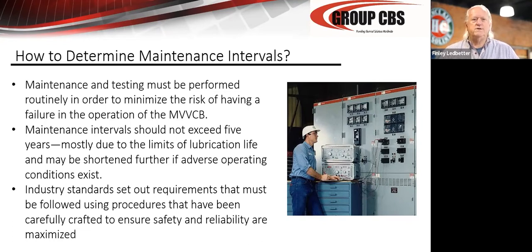I was at a power plant a few years ago, and they had spare breakers sitting on the side that had 20, 30, 40, 50 operations on them that were 20 years old. And they had breakers in service with 3,000 operations on them. What kind of sense does that make? It makes no sense. So you need to get these high operation breakers out and get these breakers with very few operations in service. And they did have a catastrophic failure, and it was one of the high interrupting breakers. And that's another story, but it's a good one. Let's move forward, or we're not going to get through the material.